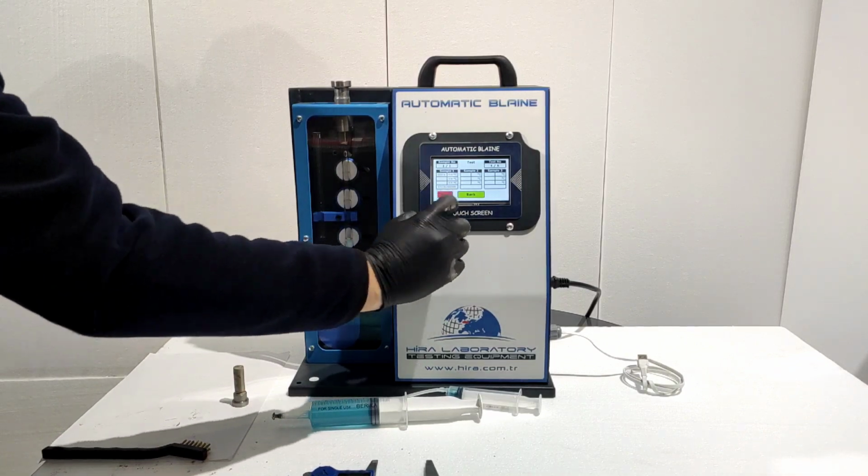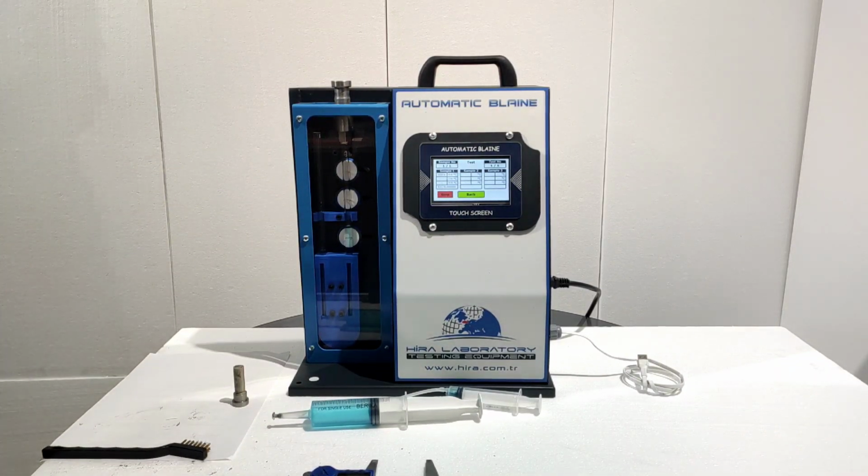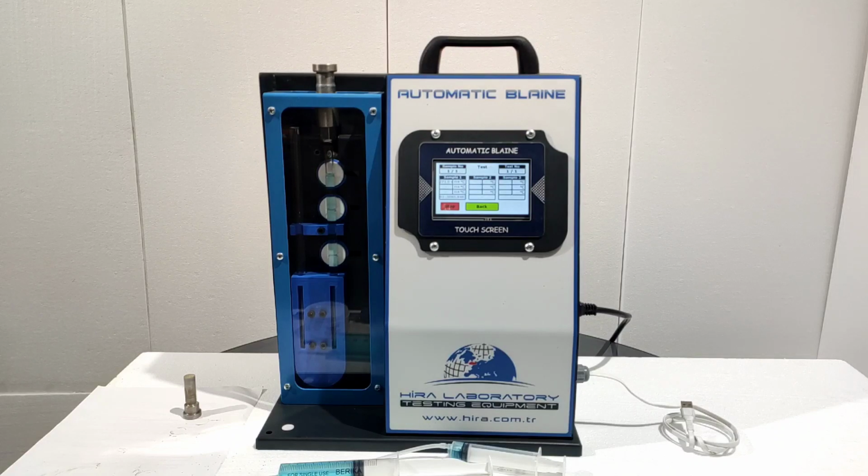According to how many samples and test numbers are selected, after the selected number of test measurements of the first sample, the cell is removed from the device, and if necessary, the second and third samples are prepared and tested by repeating the above procedures. Finally, the average value is calculated according to how many samples have been tested, and device constants are determined against the K calibration value and displayed on the screen.